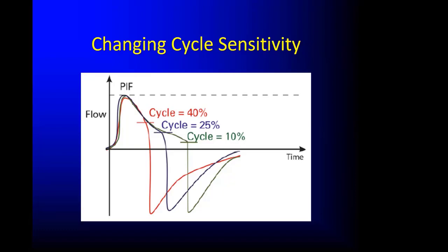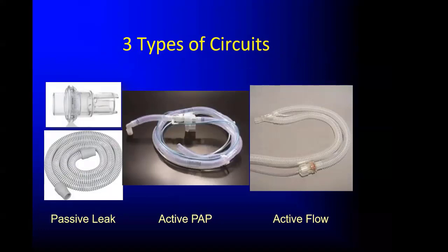All right, let's switch gears for a moment and talk about the fact that we not only have different ventilators, but we also have different circuits to use. And there are 3 types of circuits that are typically used now. One, and probably most commonly in the machines that we use, is the passive circuit. It's a single tube. It's got basically a hole in it, and that hole may be in a mask if you're using non-invasive ventilation with a vented mask, or you might be using a device called a whisper swivel or another proprietary name. But basically, this is a fixed hole in the circuit, and it's called a passive leak circuit because all you're doing is letting air go out the hole.